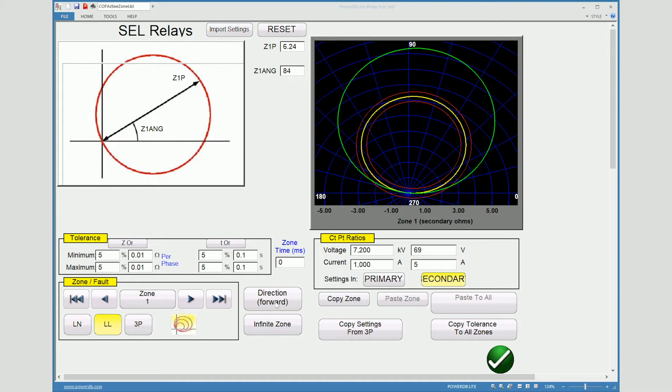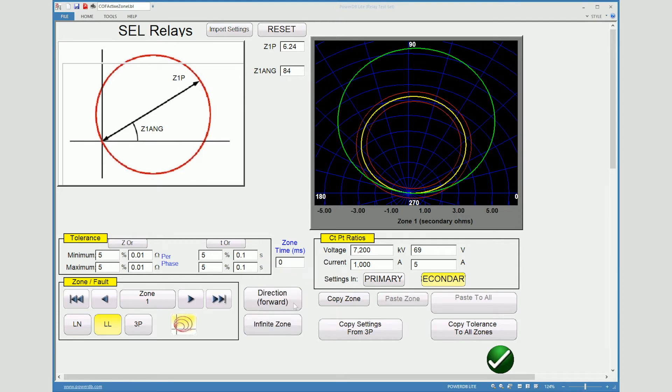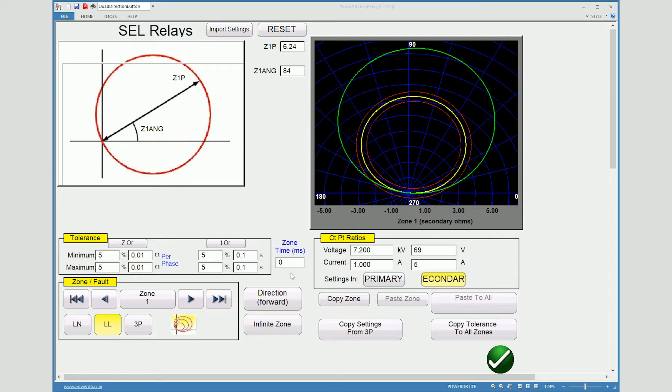We'll come over and make sure that the direction is either forward or reverse, or if that zone is actually turned off. And then we also have to have the time. So each zone has its own particular time. Now with zone one usually it's no inherent time delay so that's necessary.